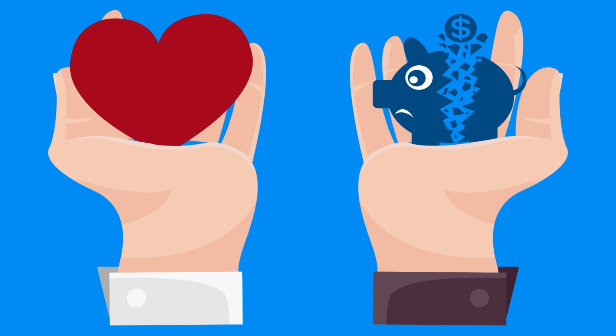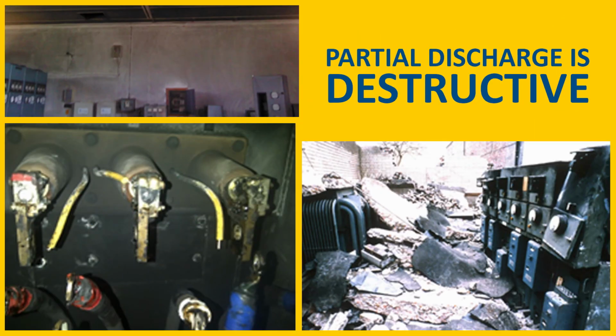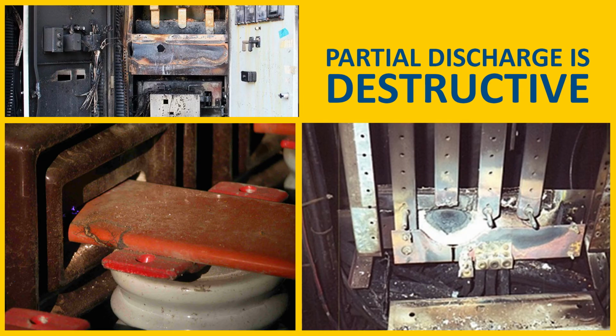So why do we want to test for it? Well, any discussion about risk must include health and safety, but it should not ignore asset reliability. One certainty is that safety and reliability risks are both linked to unscheduled downtime, costly legal exercises, and ultimately lost profit. A winning solution identifies safety and reliability as one and the same and marginalizes their impact to the other three. The consequences of allowing partial discharge to progress include damage to assets, pole fires, explosions, and deadly arc flash. As I said at the opening, unreliable electrical assets not only cost millions in downtime and repairs, they possess the potential to maim and kill our colleagues.